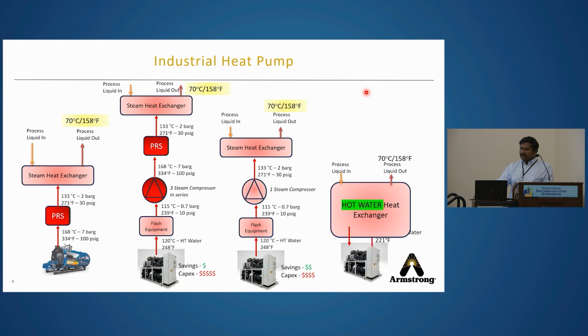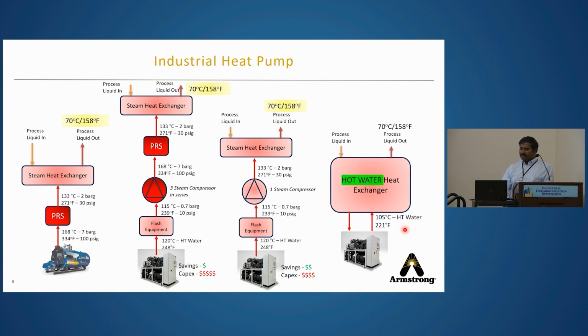So for this particular application, we proposed a high temperature pressurized hot water heat pump, which can generate high temperature hot water. They need to change the heat exchanger design from steam to a hot water heat exchanger. It requires more surface area because in hot water you have only sensible heat. So the customer is good with this because it's only one piece of equipment to heat up the process liquid to 158 degrees Fahrenheit. And the CapEx is lower because it's one piece of equipment. Operating cost is lower, and the savings is good.